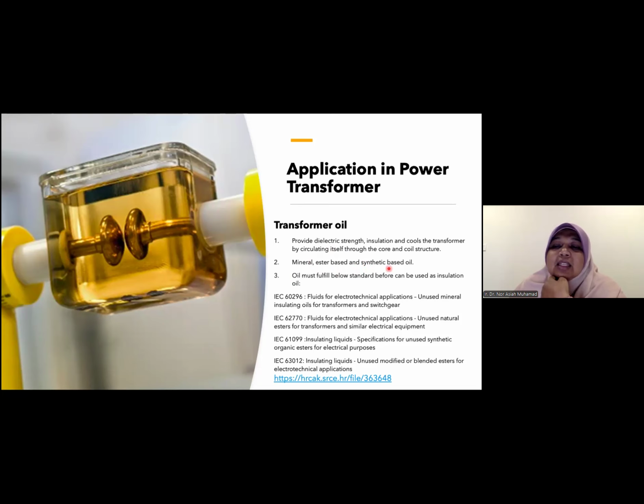There are also synthetic base oils that cover the disadvantages of ester and mineral oil, but the price is different. The oil must fulfill the standard. Before this oil can be put into the transformer, if I follow the IEC standard, it must fulfill the standard for new, unused oil, IEC 60296. There is a list of tests and requirements that this oil must go through. So if you have a new oil, like vegetable oil, soya oil, or cooking oil, and you want to make it a transformer oil, you need to test it using the standard first and find what the properties are. Then you can do modification to improve if some properties are not good.